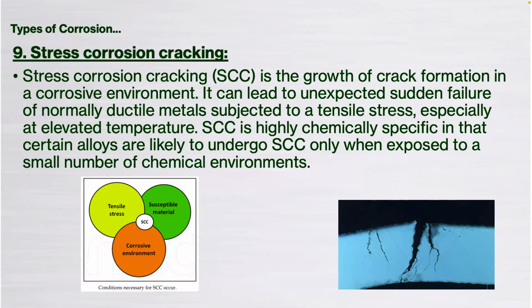So many types of corrosion. Another one is stress corrosion cracking. It's a form of corrosion. So typically we see this with bridges that suddenly collapse. But within a closed loop system, you would normally see this either in maybe a boiler failure, typically a stainless steel boiler. Perhaps you've seen a corrosion cracking occur, or probably going back a little while now, non-DZR, dezincification resistant brass fittings would crack. And for that to happen, you need three things really, all in unison.